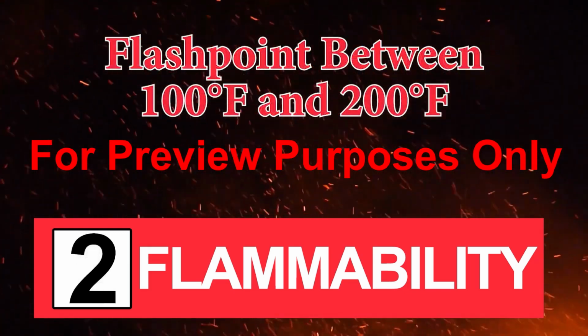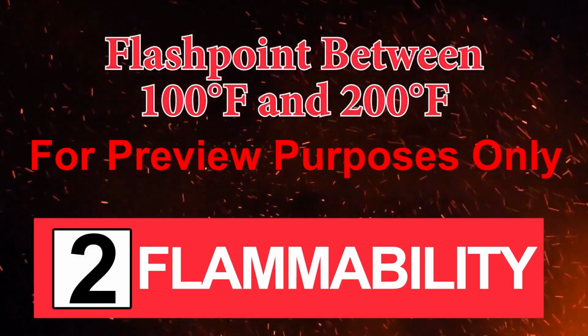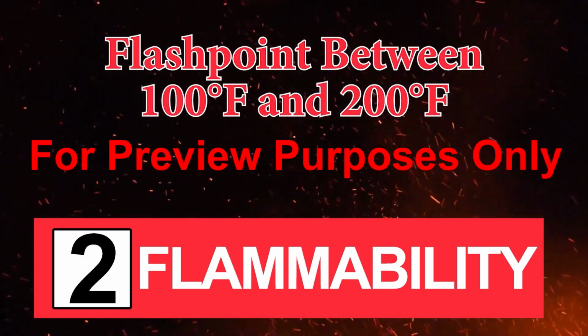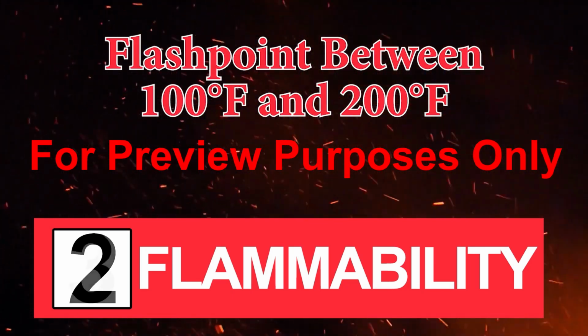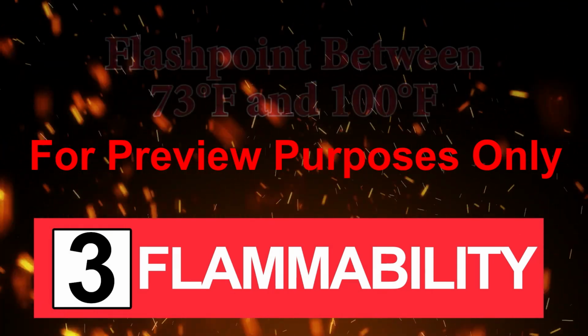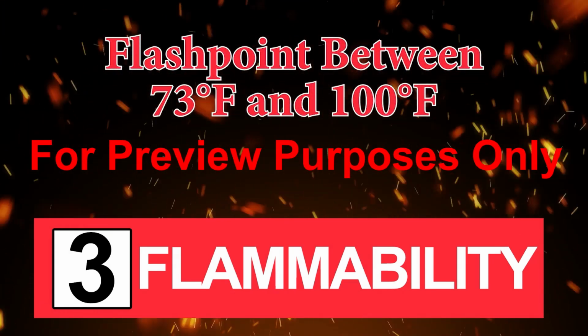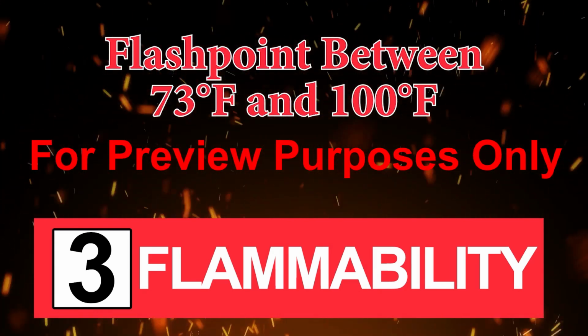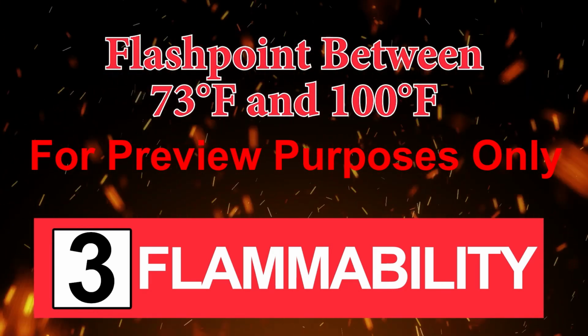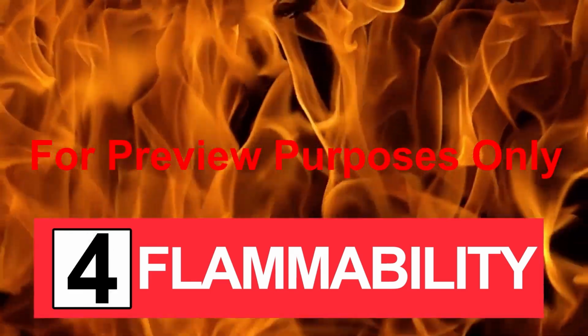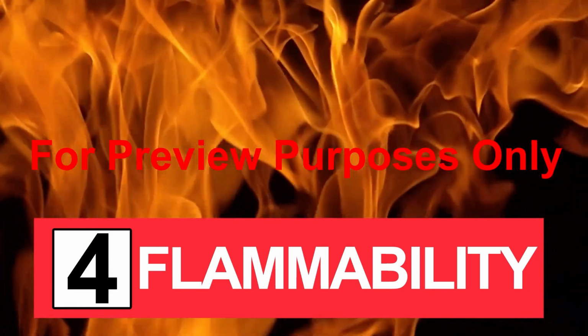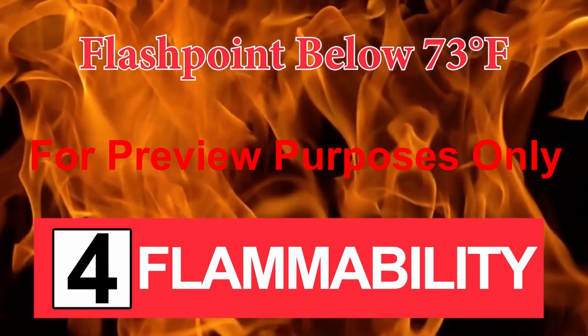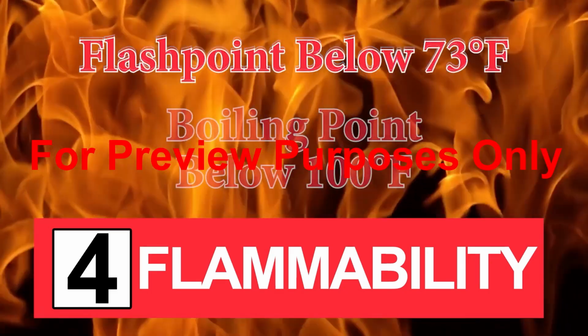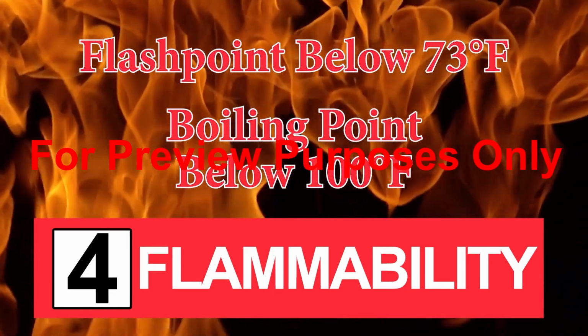Chemicals with flash points between 100 and 200 degrees Fahrenheit are designated as a 2, which are more likely to ignite when heated. And 3 identifies substances with flash points between 73 degrees and 100 degrees Fahrenheit, which means they ignite fairly easily at normal temperatures. Materials that are most likely to burn are coded with a 4, which indicates that a material has a flash point below 73 degrees Fahrenheit or a boiling point below 100 degrees Fahrenheit, making them extremely flammable.